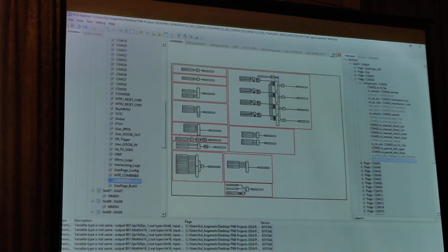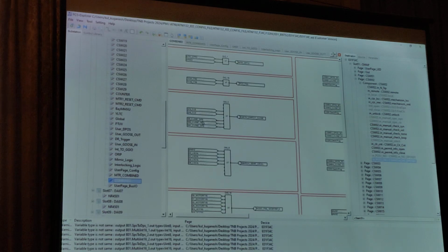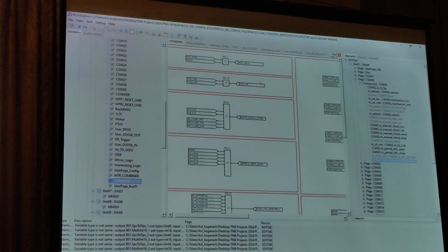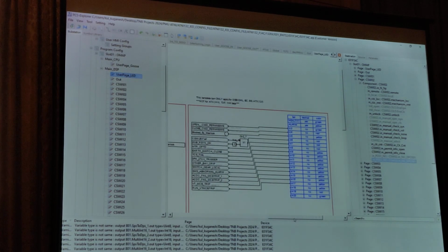Okay, for combine, combine is basically just a page where the signals are combined. Let's say TCS has 2 signals. We give them an OR gate and make it 1. So if either one is high, the TCS fail will be high. This makes it easy for us to map them into the LED page, so that the LED page looks neat and simplified.